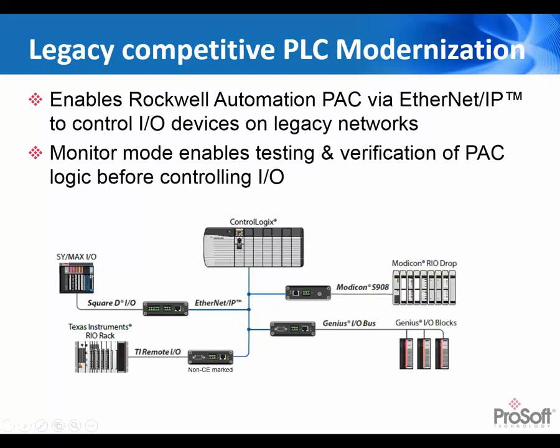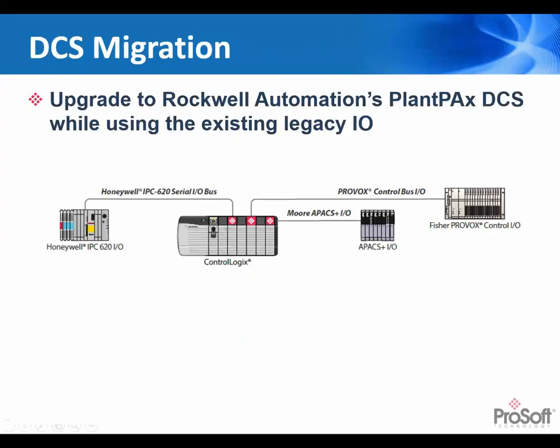That way, if anything does go wrong, you can put the legacy competitive controller back, keeping everything working whilst you re-verify the code, and then test it again and put it back in to control. The controllers can go back in to control the existing I/O, and then you can begin to change the existing I/O one rack at a time. So it's for use as a phase migration strategy again. You can also use this strategy to change out legacy DCS systems.